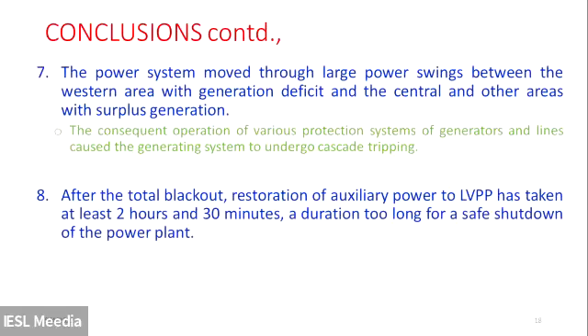So continuing with the conclusions, once circuits 1 and 2 are gone, for the power flow that took place, the only rescue path was via the Kothmale New Anuradhapura line, where there was only one circuit, and we could see very high currents, with the current reaching 2,400 amperes and coming back, with current maximum and voltage minimum, then voltage maximum and current minimum, which is a power swing. And that was a transient unstable power swing. I think CB will show you the details. So this was there. And finally, that line also got tripped by the operation of the distance protection.